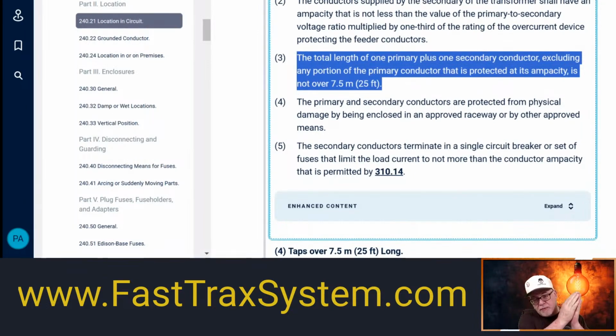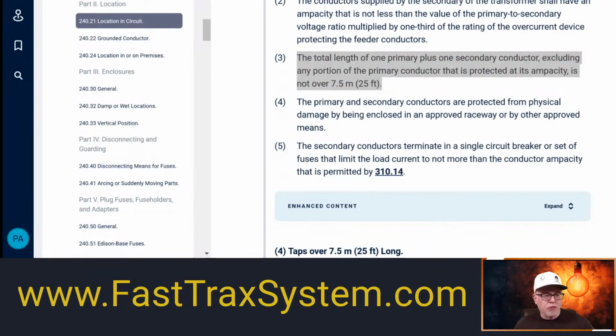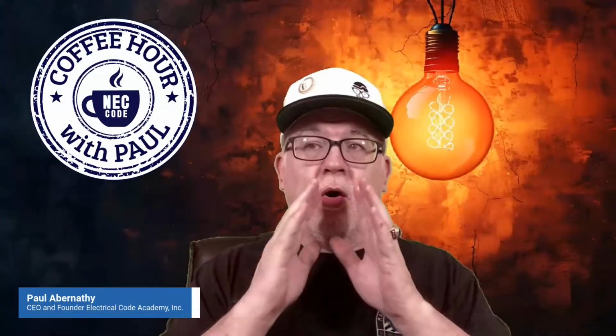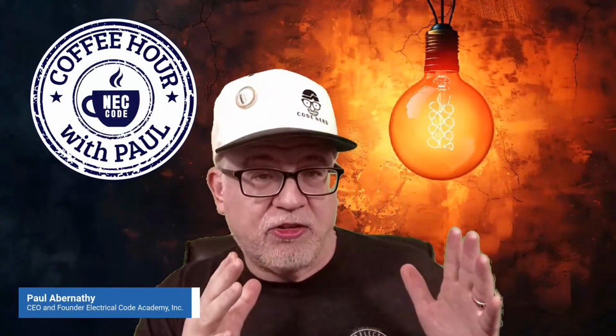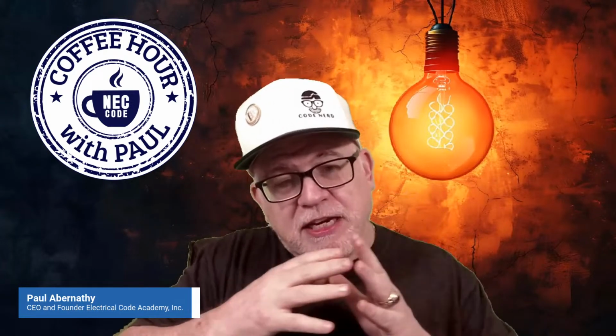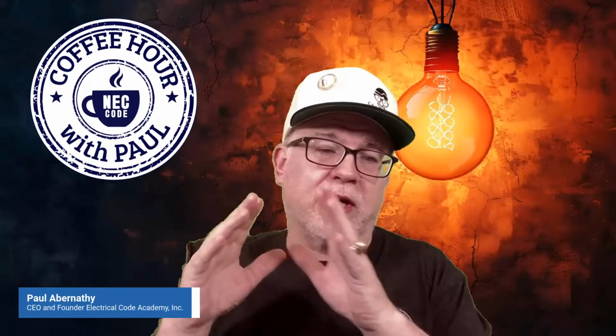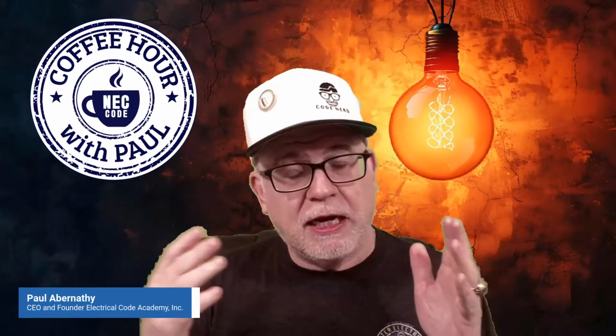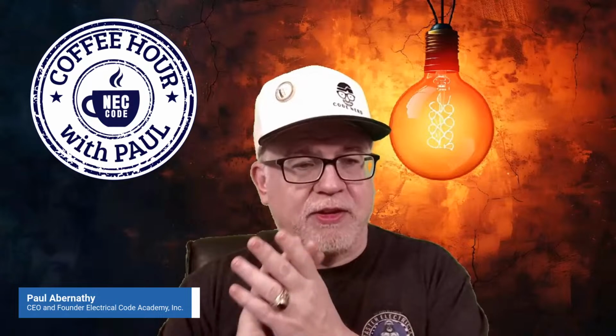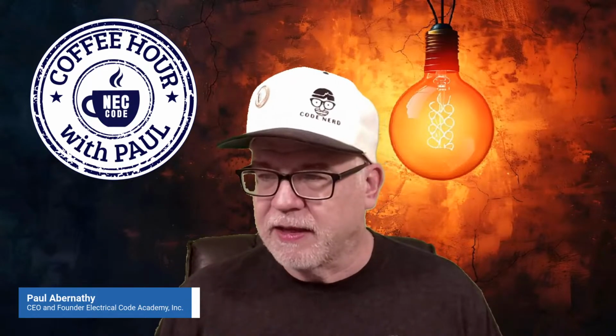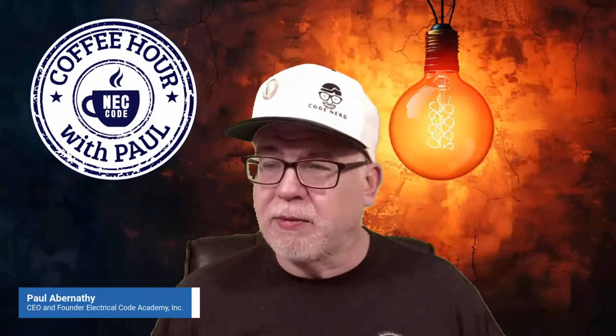So whatever from the primary side tap down to the transformer, including the secondary conductors, that maximum distance cannot exceed 25 feet. And this is probably a good example of where you are not going to exceed that on the secondary. You're probably going to use all of that distance you can on the primary side, because you're probably tapping in the trough somewhere and you need to move it down and have a location where you can put that transformer, and then you'll change over and have the transformer, and then you'll have the panel after it for the secondary. Okay, so usually that distance is all going to be within 25 feet.